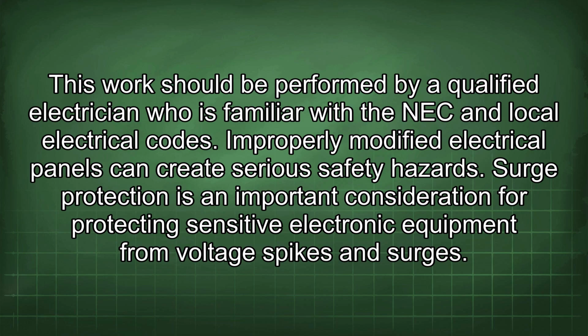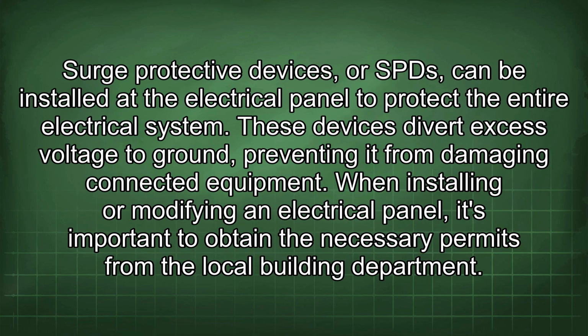Surge protection is an important consideration for protecting sensitive electronic equipment from voltage spikes and surges. Surge protective devices (SPDs) can be installed at the electrical panel to protect the entire electrical system. These devices divert excess voltage to ground, preventing it from damaging connected equipment.